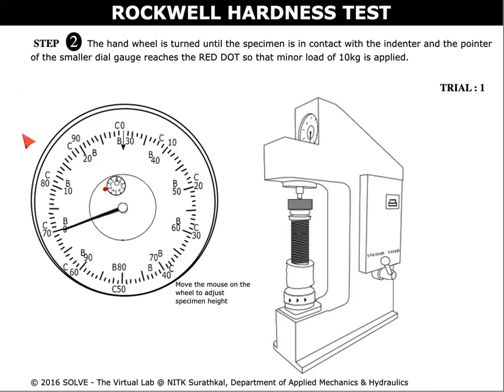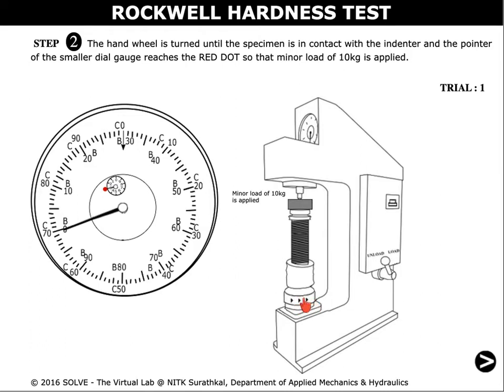Once the specimen is placed in the supporting table, turn the hand wheel by moving the mouse pointer until the specimen is in contact with the indenter and the pointer in the smaller dial gauge reaches the red dot, so that a minor load of 10 kg is applied.